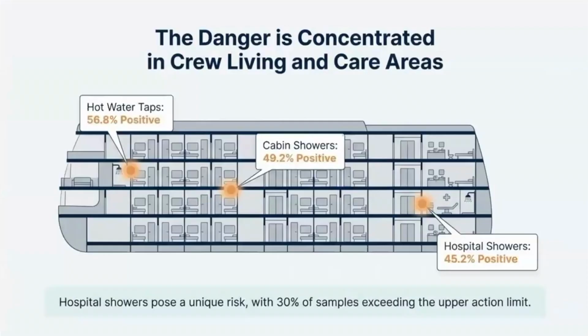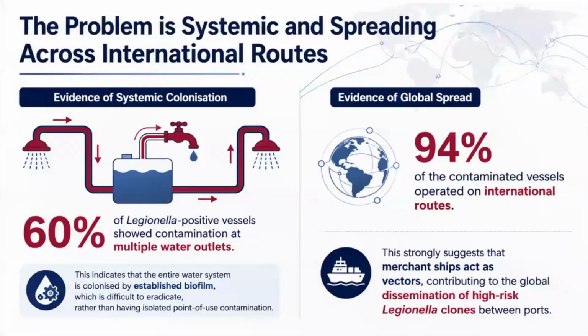The areas where the samples showed the most problems were in hot water taps, over 50% positive, showers in the cabins, just under 50% positives, and hospital showers, which is an extremely dangerous area. And the problem was systemic: 60% of the Legionella positives showed contamination at multiple water outlets.